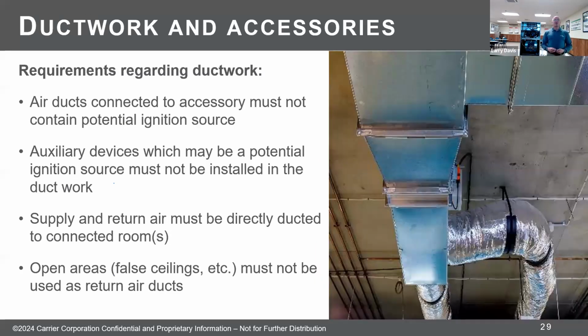All right, ductwork. A lot of questions on this slide, and I don't have a lot of answers. We're going to talk a little bit about accessories like air cleaners, air purifiers, humidifiers, things like that. We have to verify that there is not a potential ignition source there. We're using our ductwork to dissipate our refrigerant if we have a leak.